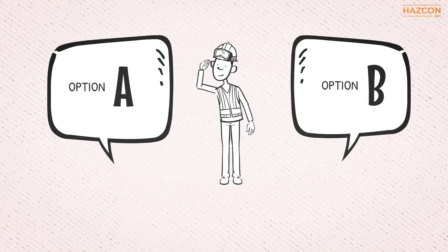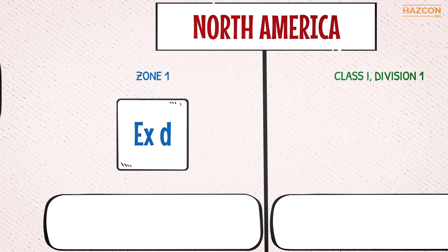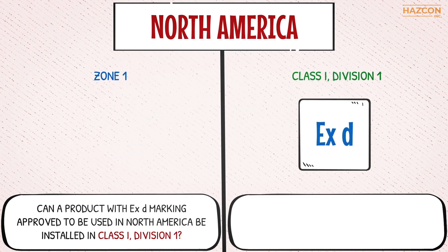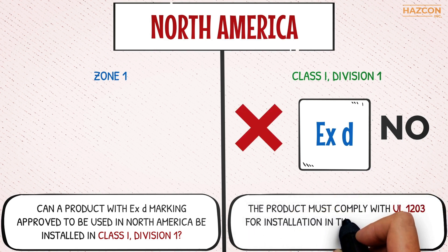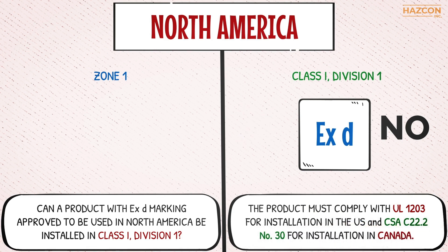Now let's answer some important questions about these two different terms. Question one: can a product with Ex d marking approved to be used in North America be installed in a Class 1, Division 1 area? The answer is NO. Remember that in order to get a product installed in a Class 1, Division 1 area, the product must comply with UL 1203 for installation in the US and CSA C22.2 No. 30 for installation in Canada.